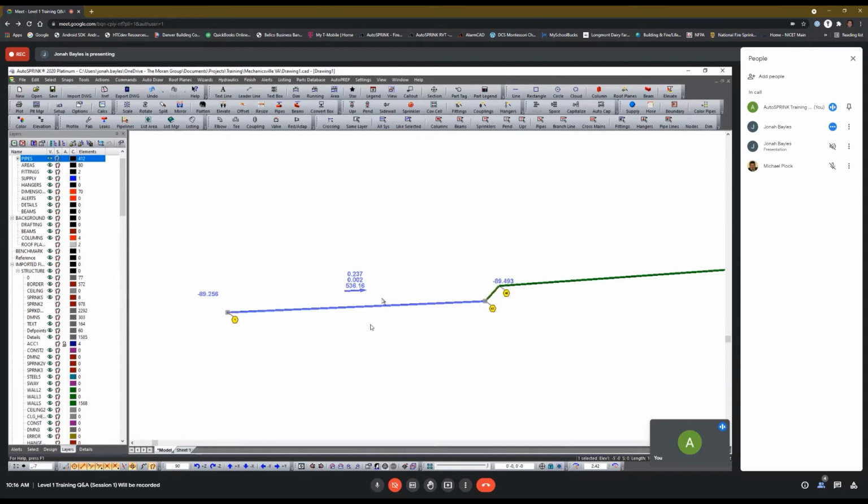When we select pipe segments, we only ever get required pressure, calculated pressure loss, total pressure loss, and the flow rate. So it is normal for those two top values in the center of the pipe segment to be relatively small, because that's the total pressure loss and calculated pressure loss per foot length.